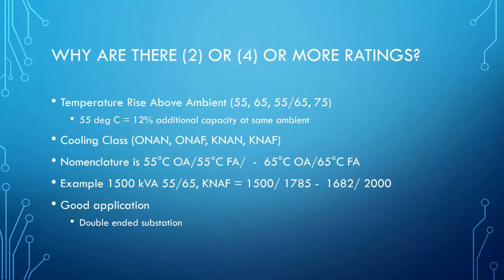If you order a 3000 kVA transformer and it is a plain Jane 65 degrees C rise transformer, it is going to rise 65 degrees above ambient when you put 3000 kVA of load onto it. And this transformer will last 25, 30 years. There are folks, though, who are not comfortable with that and who want even more capacity out of that transformer, or have an ambient temperature that exceeds what the ANSI standard calls for.